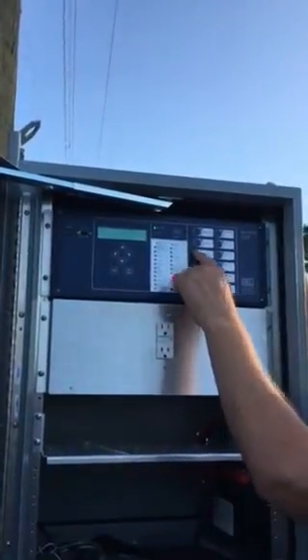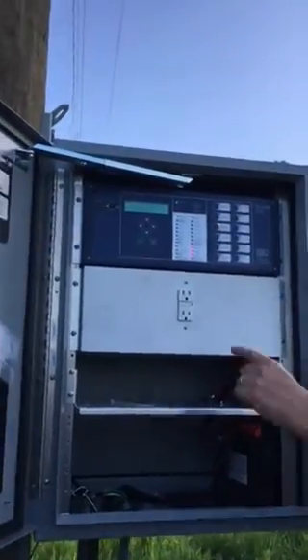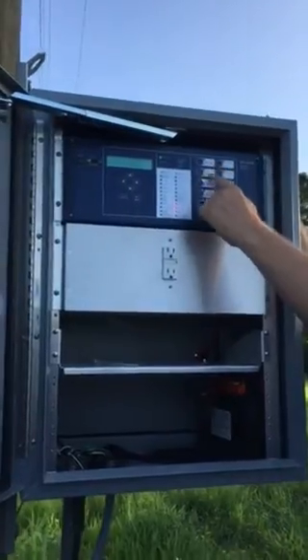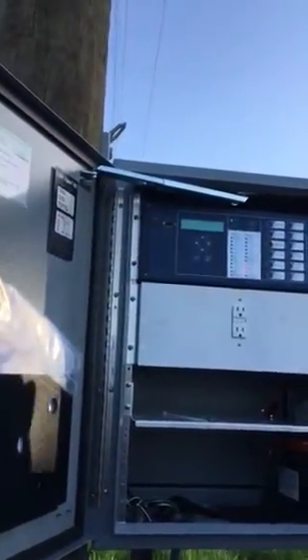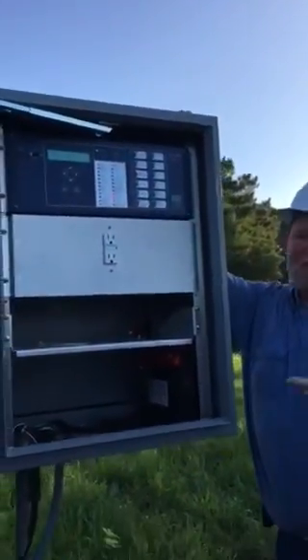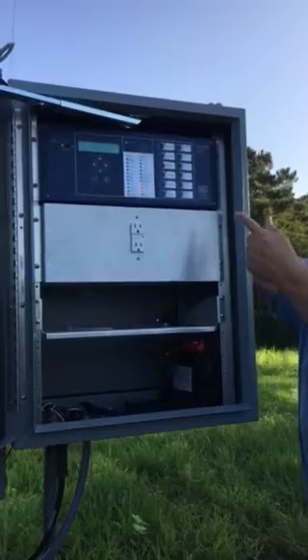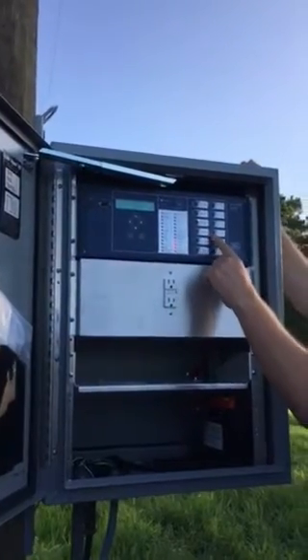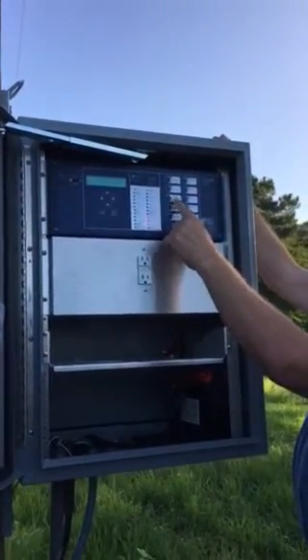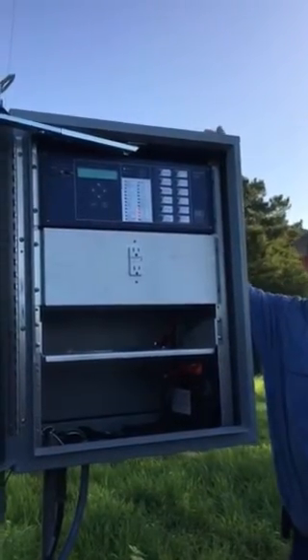That's kind of confusing. Why didn't they put remote enable and disable on there? That's the programming, I don't know. On our breakers, you've got enable and disable using two buttons, but they only use one on this. And this is the way Georgia Power does it. If you ever happen to be in one of their stations, whatever it says, remote enable, if the light's on, that's what it means. If the light's off, it's the other way. That's just kind of backwards from the other. Yeah, it is.